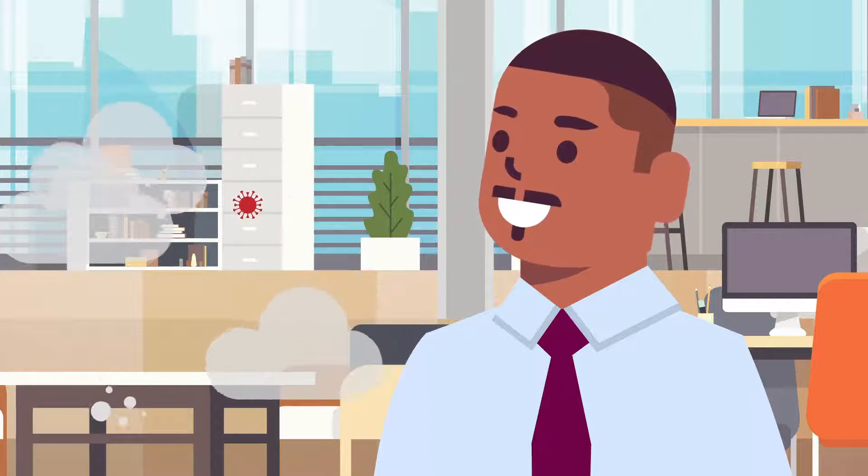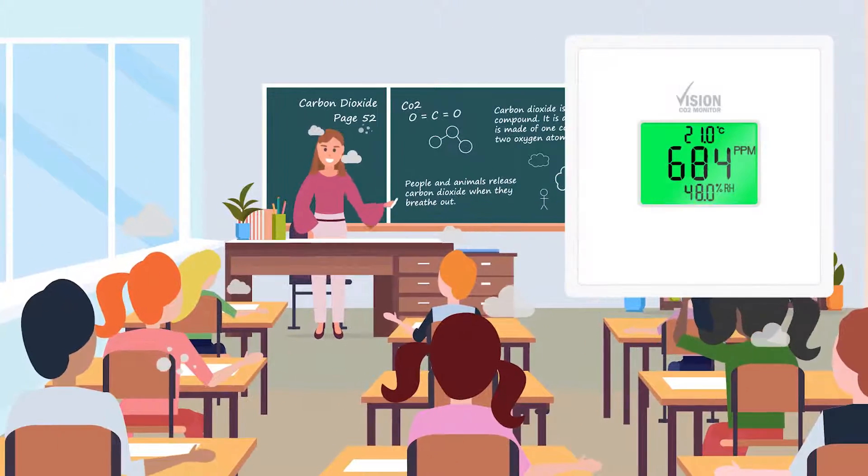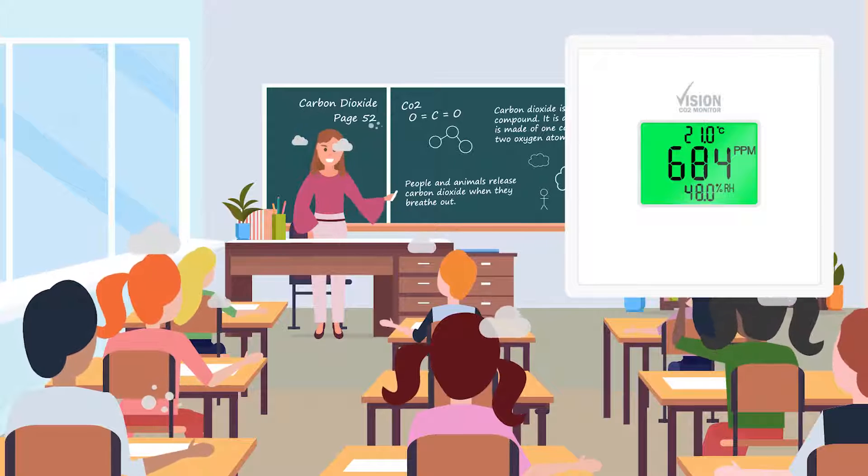CO2 can be used as a general indicator for proper ventilation in occupied indoor spaces such as classrooms and offices. If there are elevated CO2 levels, this means the air we are breathing out is not being removed, which could contain other contaminants or even viruses.